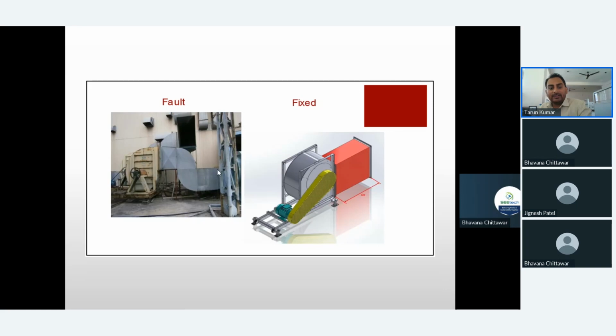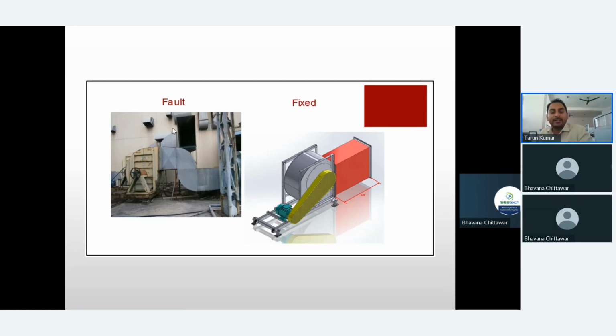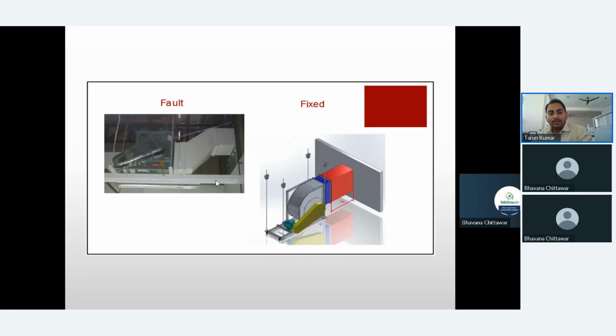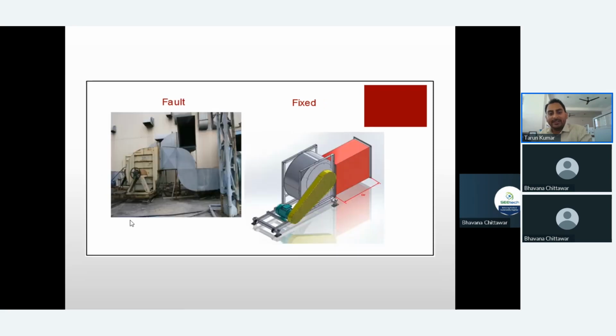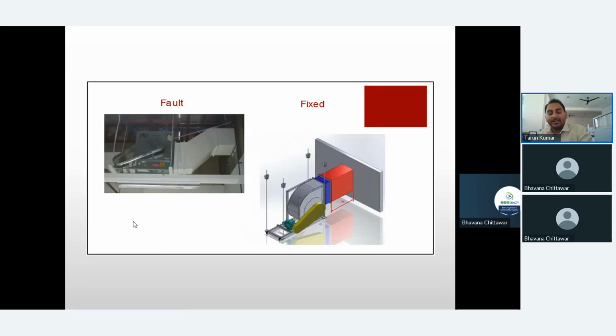Then further to that, you can see this again. They had taken the 90-degree fan orientation, but they would have gone with the 270-degree fan orientation, and then these immediate 2-3 bends would have been avoided, and your power consumption becomes less than this system. So you can see the other photograph also. Here they were taken wrong. Here it should have been 270-degree rather than 90-degree, and here they have taken 270-degree rather than 90-degree.